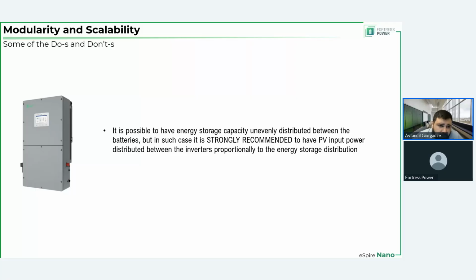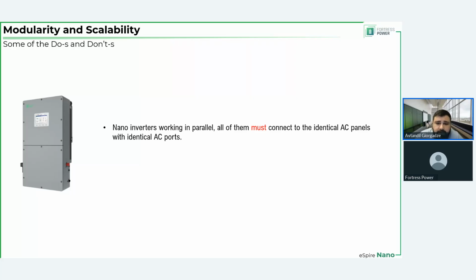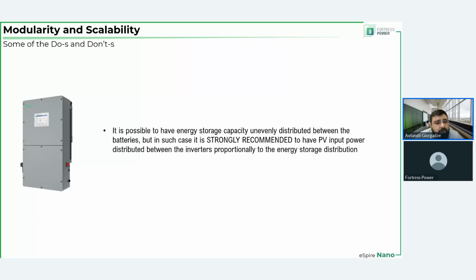Also, I mentioned before that it is possible to have different storage capacity per inverter, provided that each inverter has only one type of batteries connected to it. I provided an example of one inverter having 80 kilowatt hours of capacity coming from two 40 kilowatt hour batteries, and the other one having one 60 kilowatt hour battery.